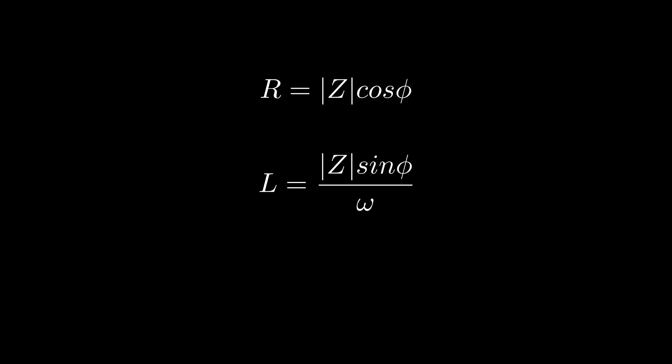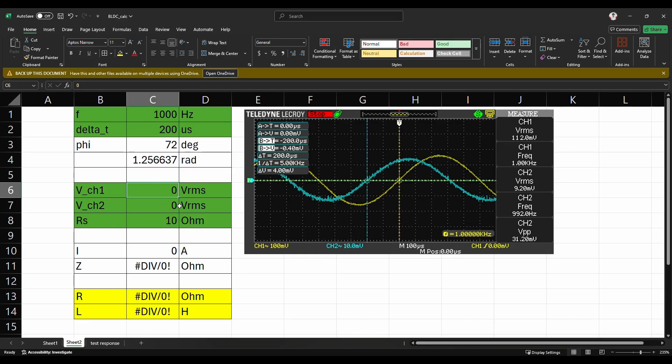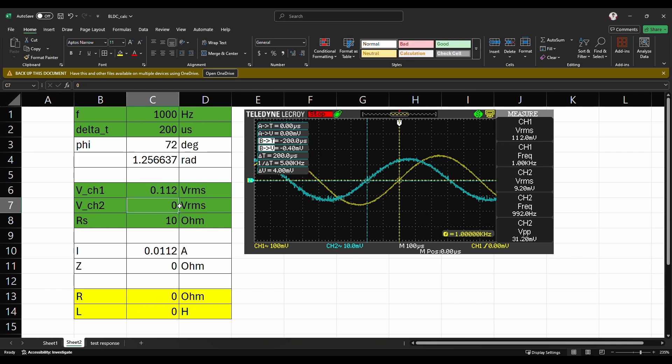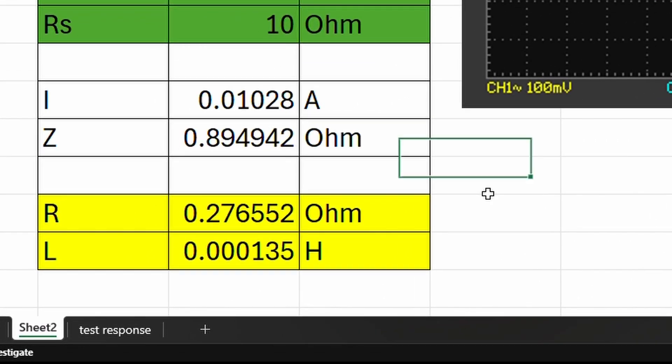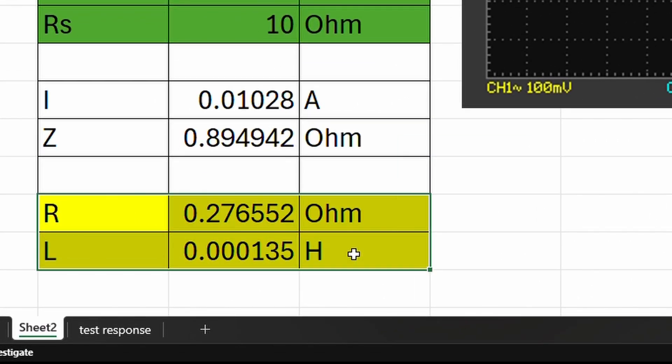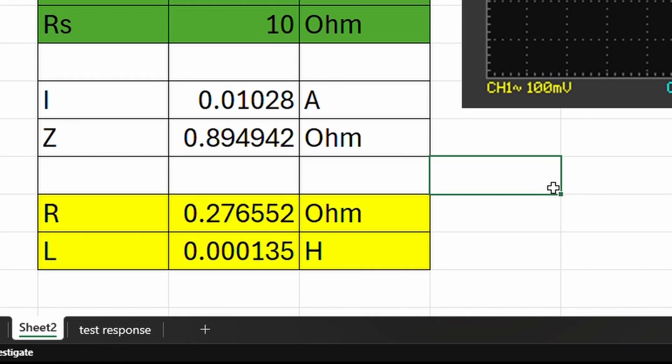In this way, we can directly obtain the resistance and inductance values of the motor using just an oscilloscope and a function generator without needing an accurate RCL meter. After performing the measurements and calculations, the resistance value obtained was 0.276 ohms and the inductance was 0.135 millihenries.